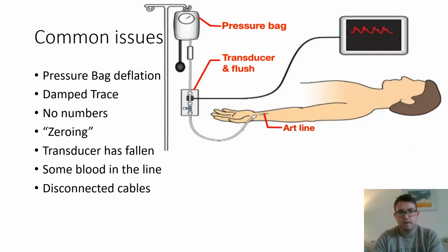Sometimes we speak about damped traces. That's whenever our wiggly line is less wiggly, so we don't get a very good representation of the top and bottom numbers. These numbers will go more to the mean pressure. Sometimes there are no numbers on the screen, and this may be because there's a disconnection of the cables, or that the set has not been properly zeroed.